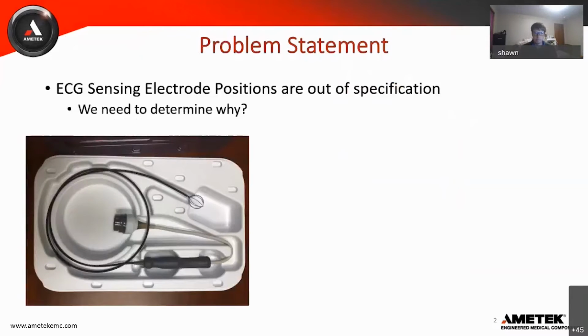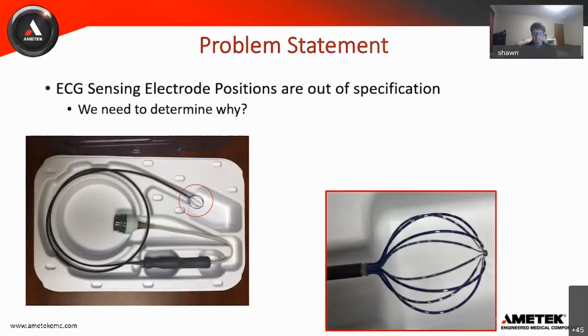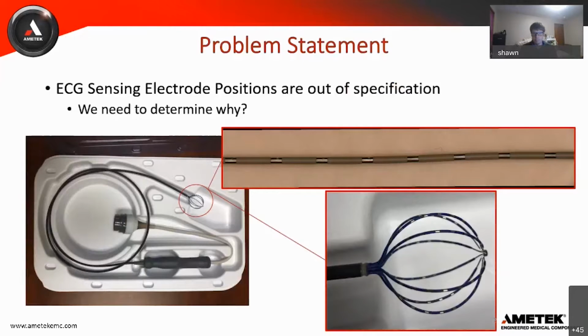This is an example of a cardiac mapping catheter. These catheters are used in the heart to read the ECG signals of the heart and create an anatomically representative image, showing where an arrhythmia may be present. Electrode locations are critical as the system uses the electrodes to accurately represent cardiac maps created and interpreted by the electrophysiologist. Our engineers are seeing that the electrode positions on the spline assembly are drifting out of specification on the high side.